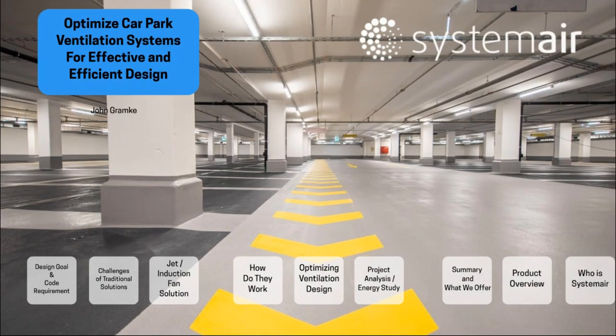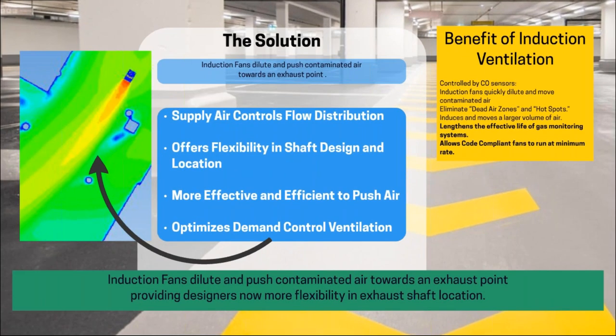What we've recognized as the correct and proper solution are jet fans - whether a high-thrust axial jet fan or a high-induction centrifugal jet fan. Jet fans use the supply air to control the flow distribution, and because you're manipulating the natural airflow path to move where you need it to go to circulate and optimize the ventilation design rate, you have more effective control over that airflow. With more effective control comes greater flexibility in shaft size, shaft design, and shaft location. And from a traditional HVAC standpoint, it's more effective and energy efficient to push your air than to try to pull it.